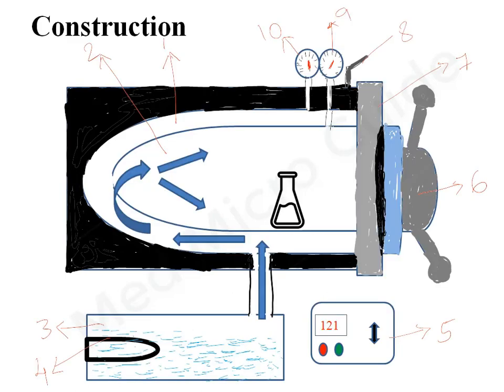The autoclave is made from either gun metal or stainless steel. It has an inner chamber in which the load is kept, and a steam jacket which covers the inner chamber. There are two pressure gauges — one for the steam jacket and one for the inner chamber. The autoclave is secured by a thick stainless steel door fastened by screw clamps and washers. There is a valve on top of the autoclave which controls steam movement. It has three modes: accumulating steam in the jacket, releasing steam into the chamber, and releasing steam from the chamber to the exterior.